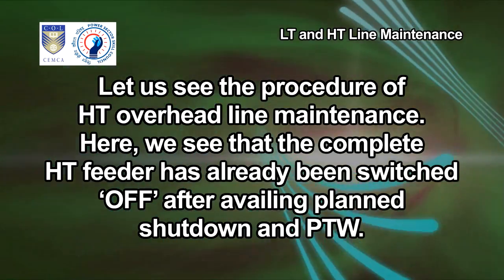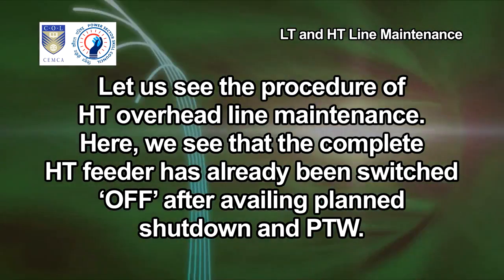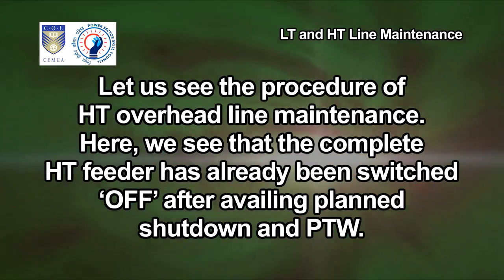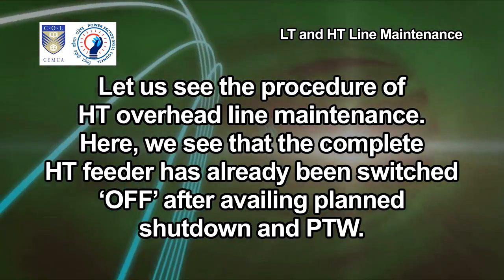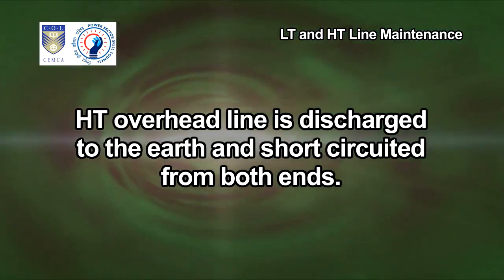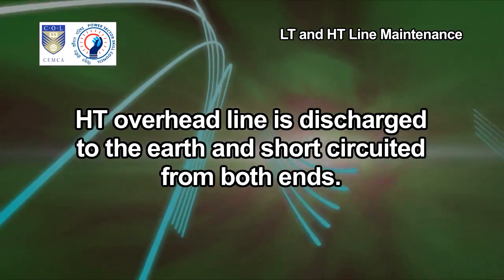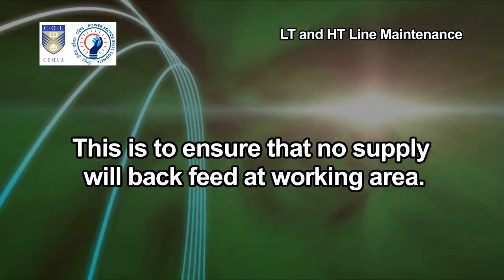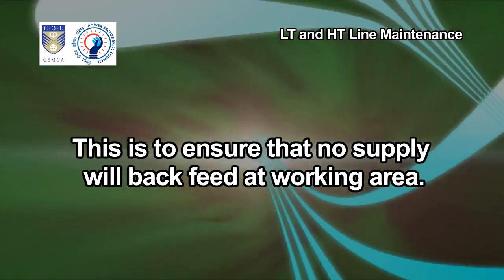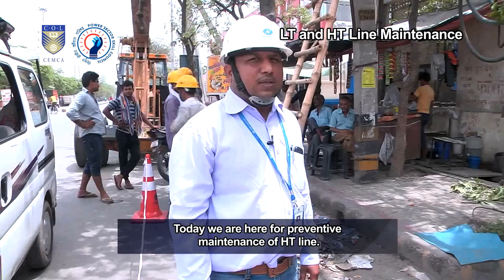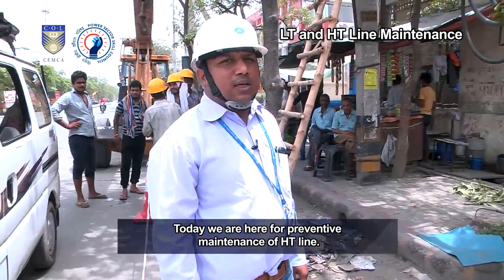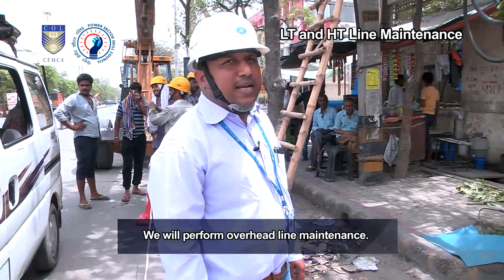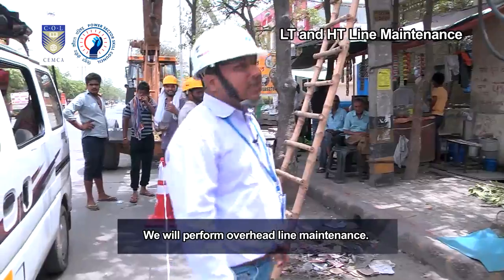Here, we see that the complete HT feeder has already been switched off after availing planned shutdown and PTW. HT overhead line is discharged to the earth and short-circuited from both ends. This is to ensure that no supply will backfeed at working area. Today, we are here for preventive maintenance of HT line. We will perform overhead line maintenance.